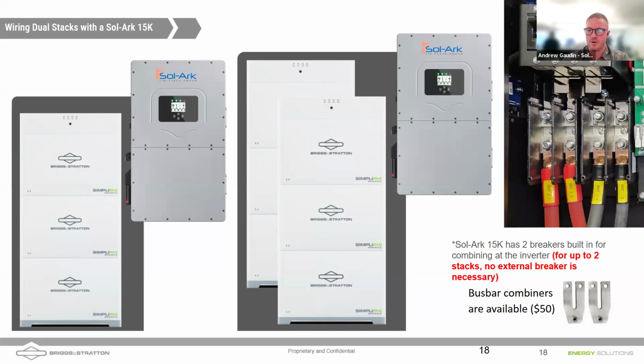Also, we've changed some components as we've gone to more domestically sourced parts for our inverters. The physical properties of the terminals have changed a little bit as well. So some of those bus bars may not even fit properly and have clearance on those terminals. If those terminals are touching some of the plastic, obviously that's starting to get hot and that's going to cause you problems as well. So it's always going to be safest to use two parallel sets of wire. That's how it was really designed.